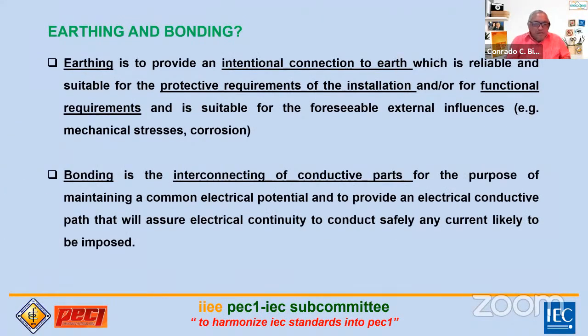Earthing and bonding, these are two words we should not mix up or reverse. Earthing is to provide an intentional connection to earth, which is reliable and suitable for protective requirements of the installation or for functional requirements, and suitable for foreseeable external influences, mechanical stress and corrosion. It's very important that the grounding rods we use can foresee corrosion happening later, or how we interconnect our earthing, because the moment this gets cut due to corrosion or loose connections, continuity of earthing is very important.